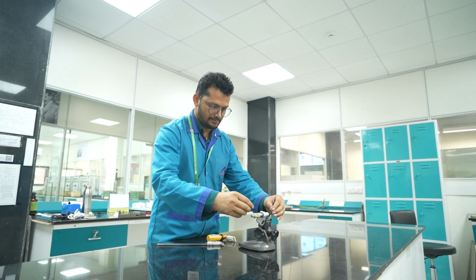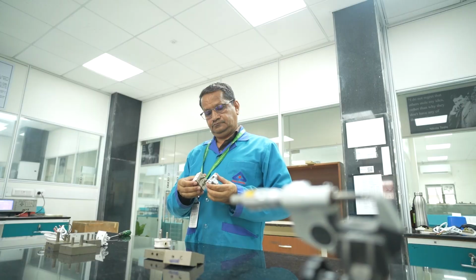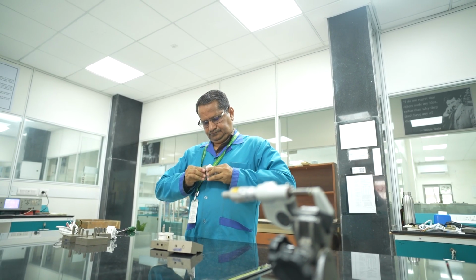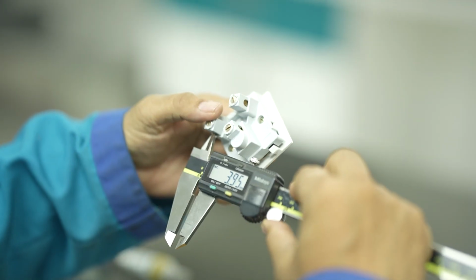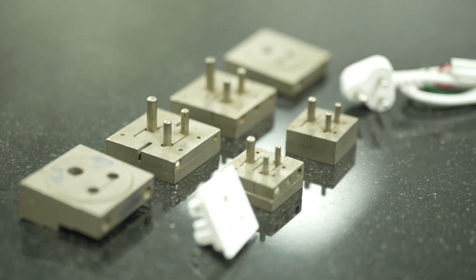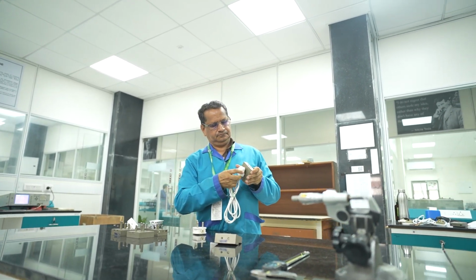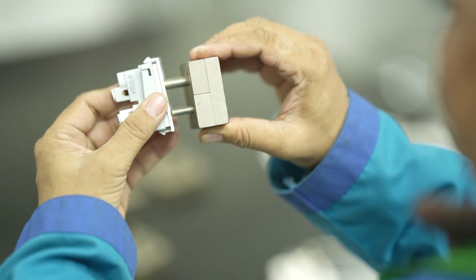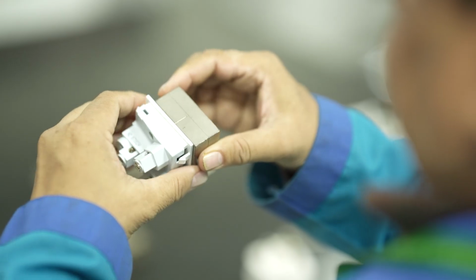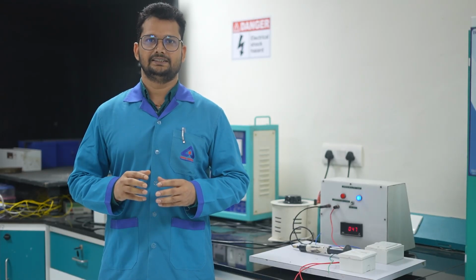Testing procedure: checking of dimensions. Clause 9. The first one is dimensions of the plug and socket outlets are verified using precision measuring instruments like vernier, micrometer and go gauges. Compliance with standard values ensures a secure fit, preventing loose or overly tight connections which could impact safety and functionality. Protection against electric shock. Clause 10. To ensure user safety, a test probe is used to verify that live parts are not accessible during normal operation. This test is critical in preventing accidental contact and minimizing electrical hazards.